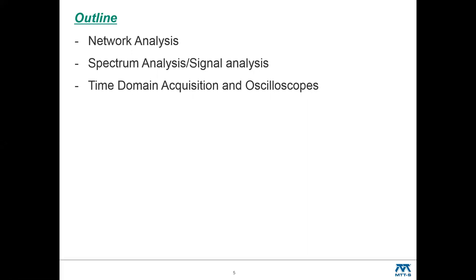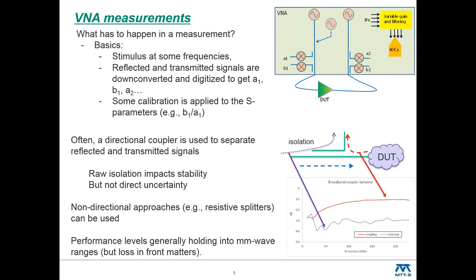We'll start off with network analysis as one of them. You may be very familiar with this kind of block diagram, where there's one or more stimulus sources, usually just a sinusoid, maybe switched, there may be lots of sources. Some signal separation devices to pull off incident, reflected, and transmitted signals. Some down converters to generate these A and B waves that can be digitized. And then some calibration is applied to take out loss in cables, mismatch in the VNA itself, and other variables.